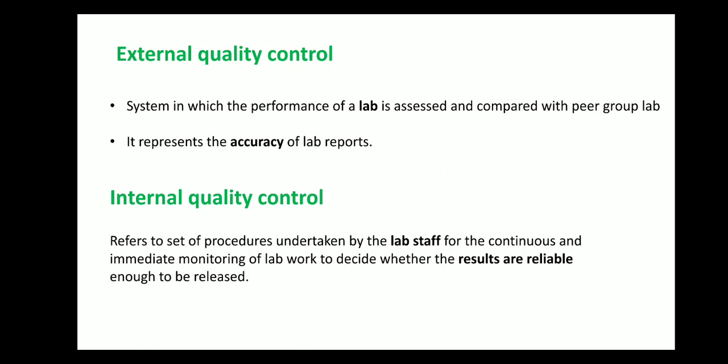Then we compare what we uploaded with the exact value. If we are accurate and precise with their expected values, then our analyzer is working properly and our report quality is good. So this is how we analyze. This is called external quality control.